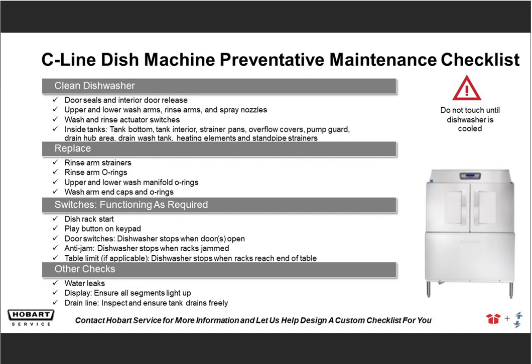The other obvious checks, you want to check for any leaks. You want to check your display. Make sure if it's supposed to say 165 degrees F, that's what it says. Check your drain line. Make sure it drains freely and that your drain in the floor is not overflowing.